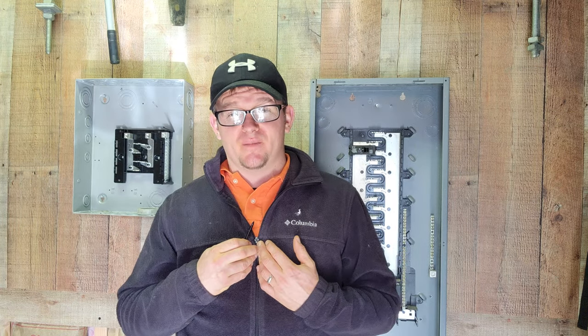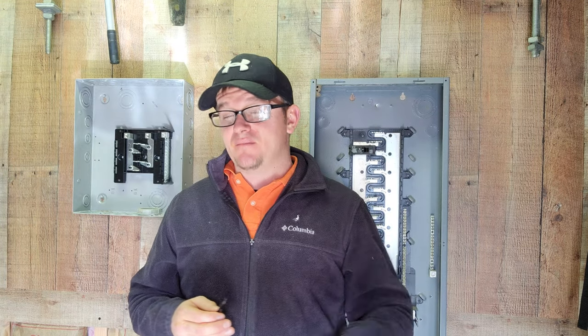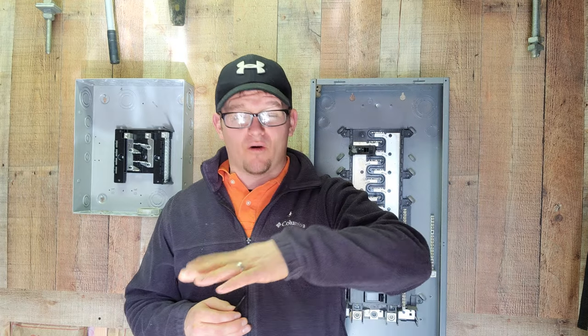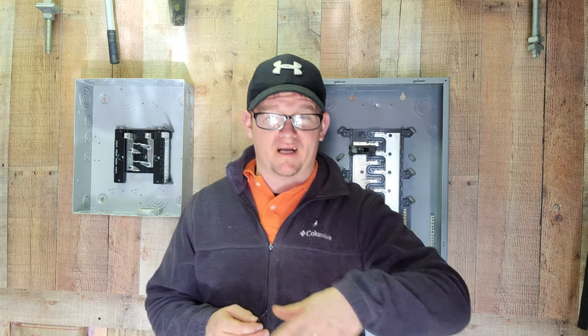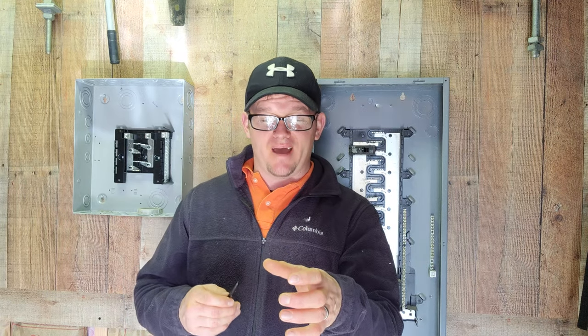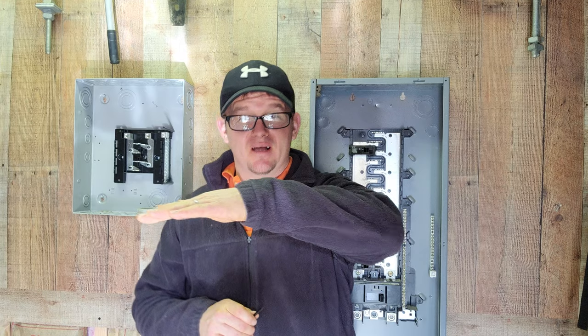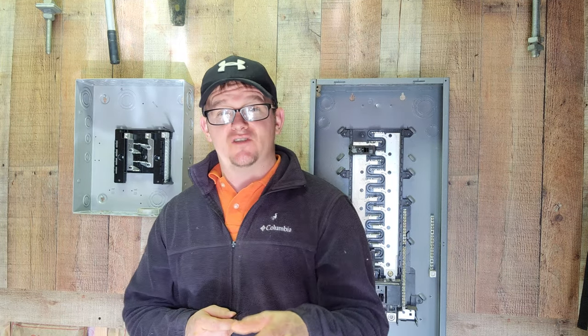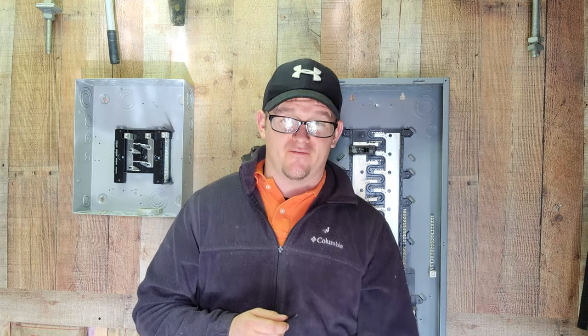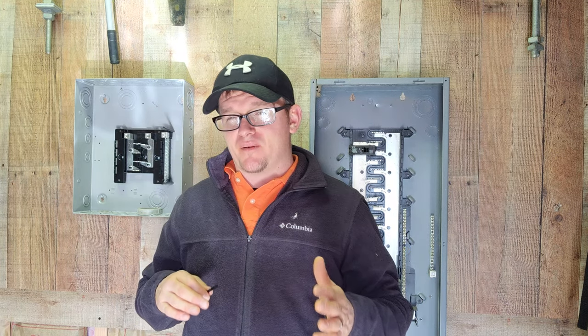A lot of electricians, including myself, we like to put our switches at 48 TTT — and what that is, is to the top. So we'll go ahead and pull our tape out, or our story pole like I've talked about in the past. We'll mark 48 inches, then we're going to bring that switch box and set it against the wall, and nail it so the top lines up with that 48-inch mark. Some guys like to put it at 52 to the top. Some people like to put it at 48 to the center or 48 to the bottom. You can do it however you want — it's all about personal preference.